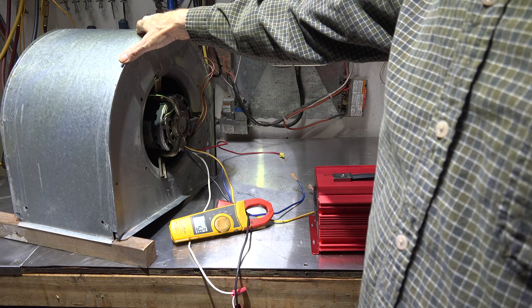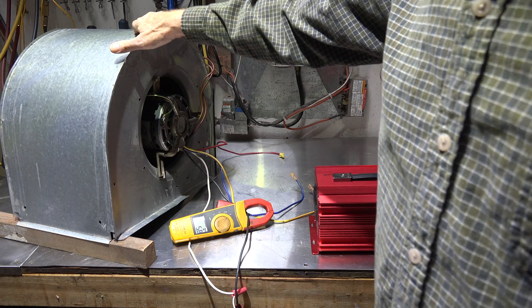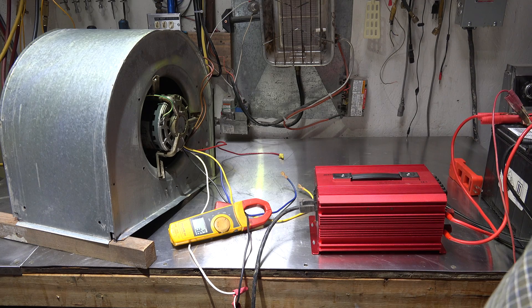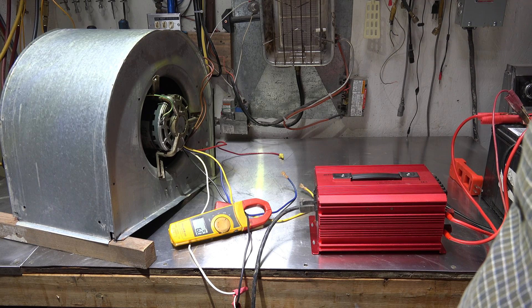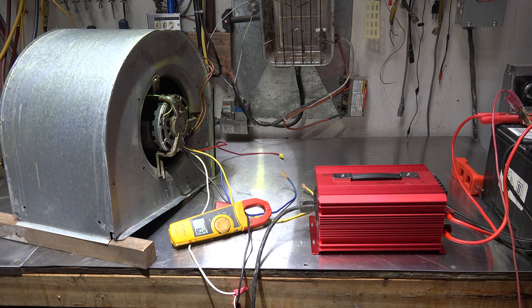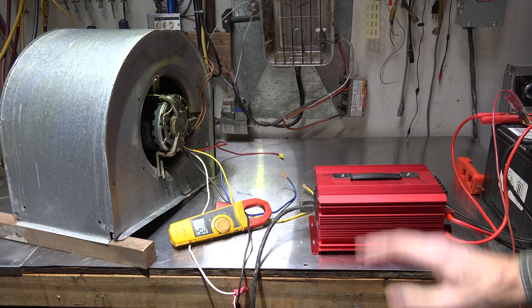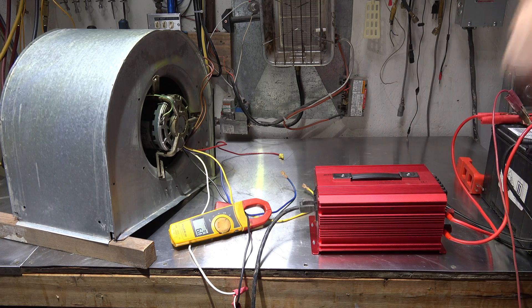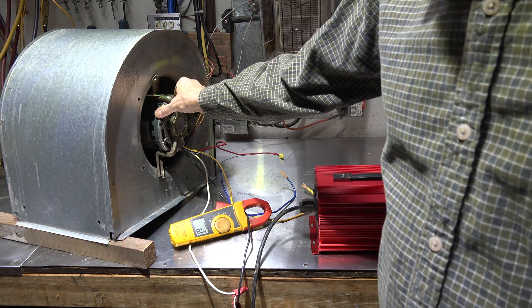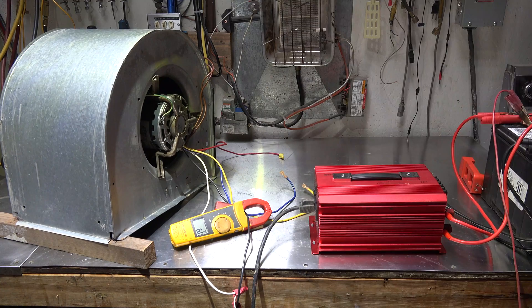So let's see what it does when it's hooked up to the inverter. Okay, the inverter is hooked up. I'm noting I'm running about 5.8 — same amperage as I was running with regular power. The motor doesn't seem to be doing anything obnoxious. It's a little hard to tell because of the vibration. Let's try another motor and see what happens.